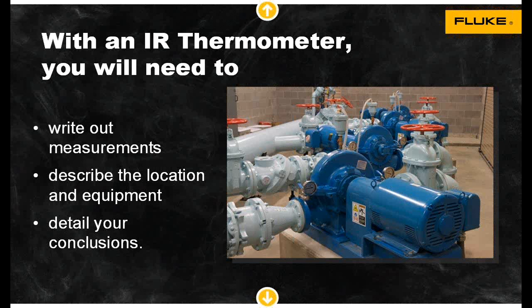With a complex piece of machinery, such as a pump set shown, it's difficult to describe the point where your measurement has been taken. If you're measuring a bearing housing without the benefit of a visual camera, it would be hard to describe the point of measurement and to duplicate that point on a subsequent visit. Detail your conclusion. Without the benefit of saving an image and the ability of software to produce a detailed report, any conclusion would be anecdotal at best.